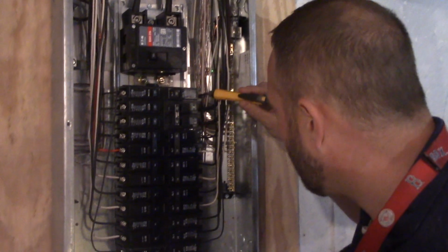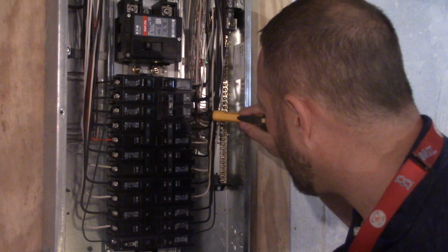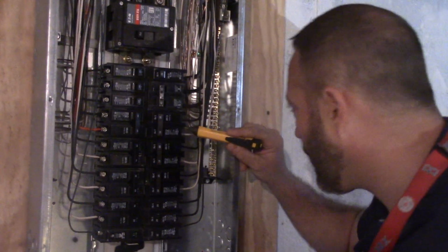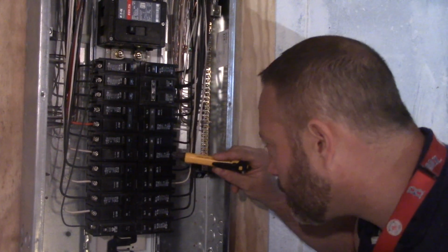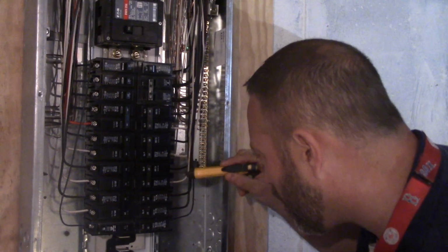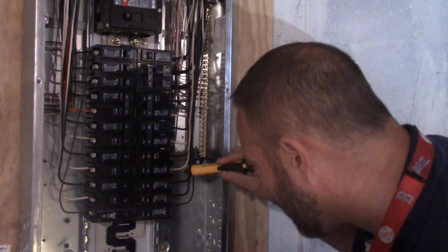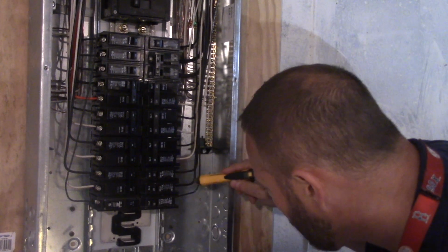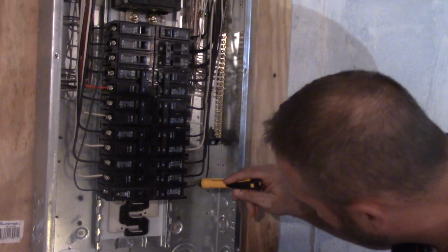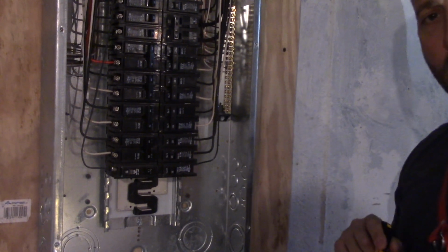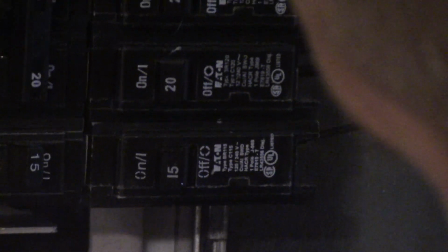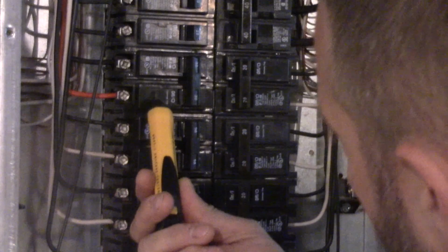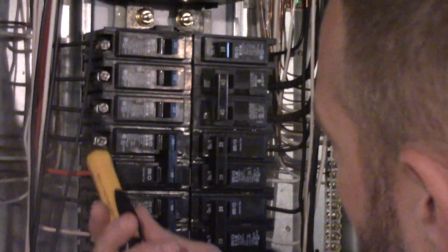So we have a 12 gauge wire here. We got the proper size for the 20. Here again we have another 12. We got a 20 amp with a 12, a 20 amp with a 12, and another 20 amp with a 12. Oh, here we have a 14 gauge wire with a 15 amp breaker, so that's definitely appropriate. And we have 12 again, and 12 again. On our 30, we have a 10.